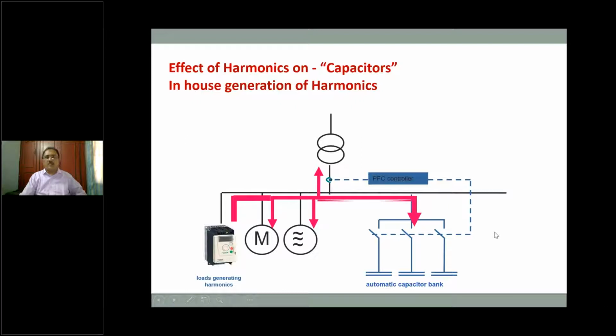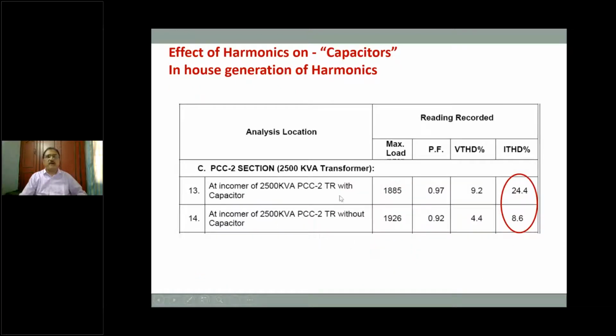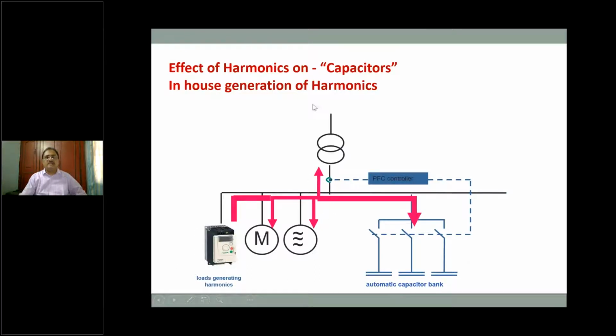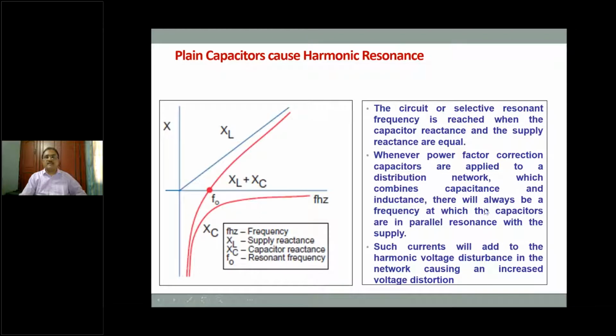It will spread. Now, because you have a capacitor in the network without any resistance or reactor in the circuit, the harmonic will get amplified because of the plain capacitor, and that will also flow through the grid. This is the problem of using a plain capacitor in a network which has a high incidence of harmonic. This is only to explain to you: on a 2500 kVA transformer, all incomer capacitors were switched on, and we found that 24.4% is the harmonic current. When we switched off all the capacitors, the harmonic content came down to 8.6%. So this is what we were trying to say in the previous slide. When a plain capacitor is there in a network with harmonic generated, the harmonic will get amplified due to resonance. This can be seen in this particular graph.